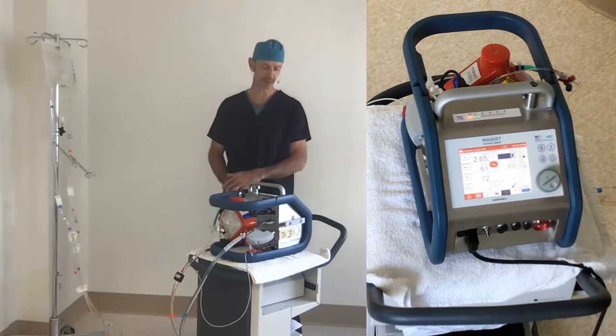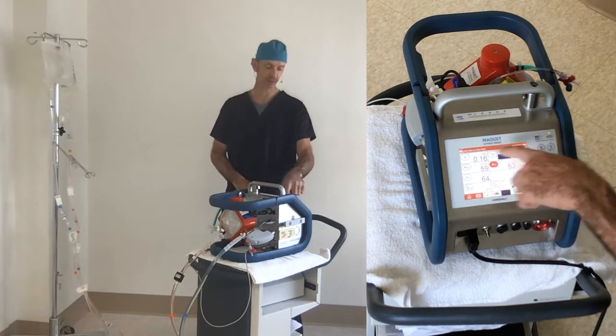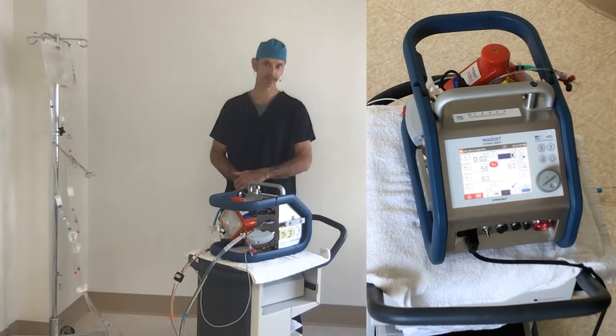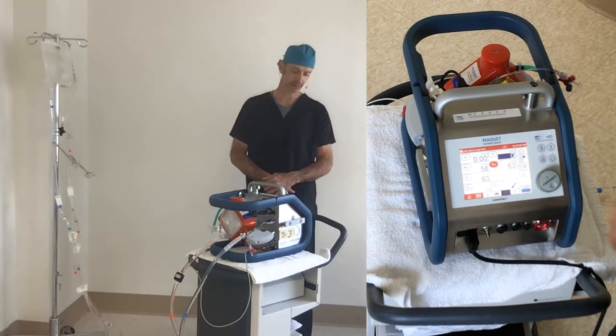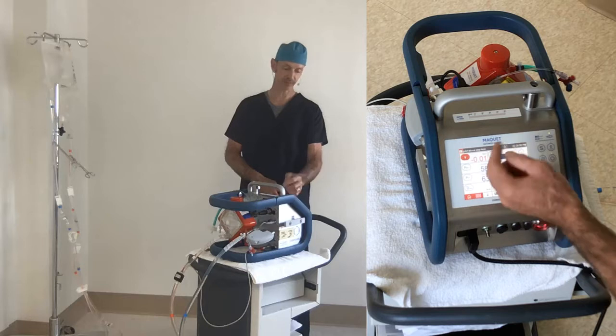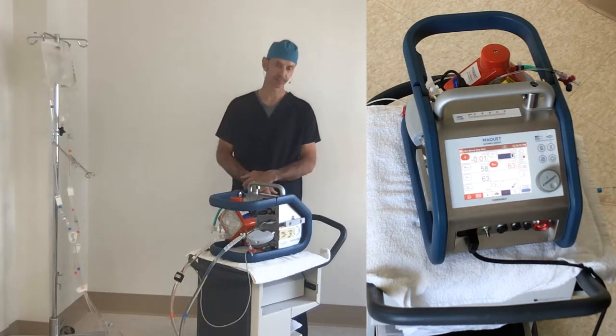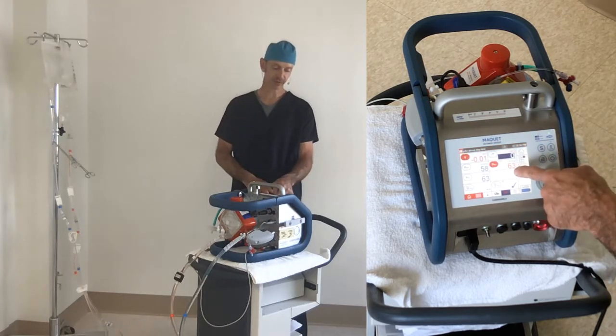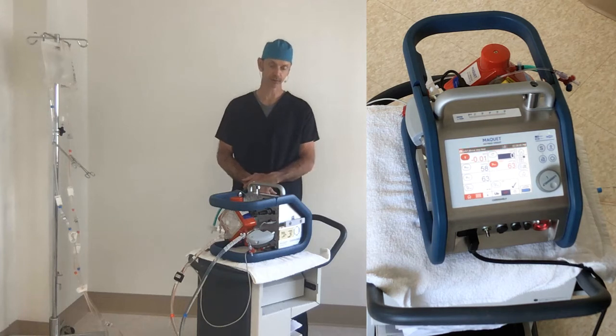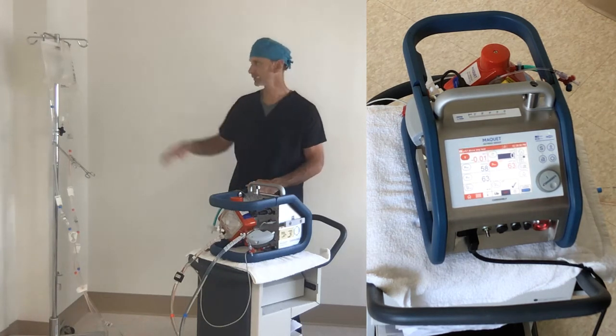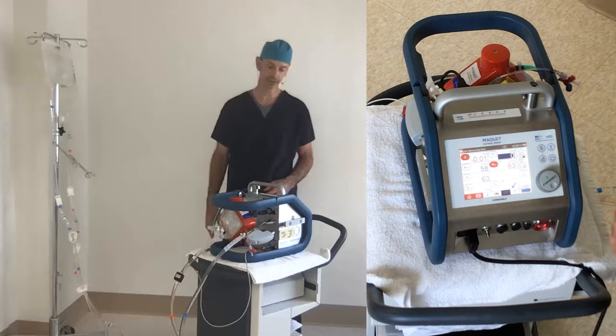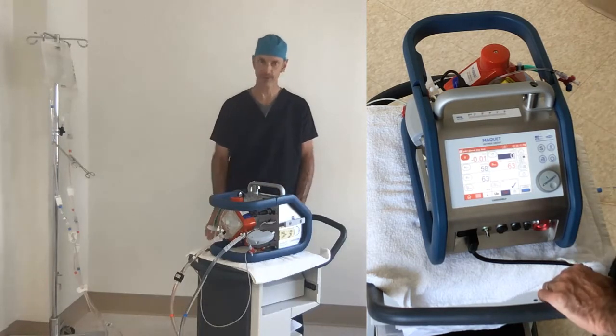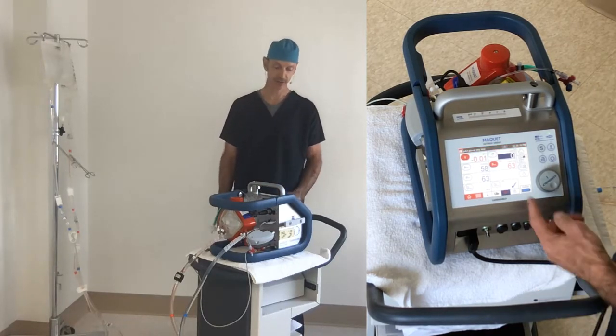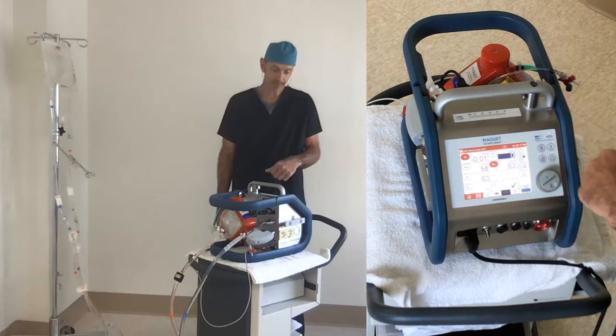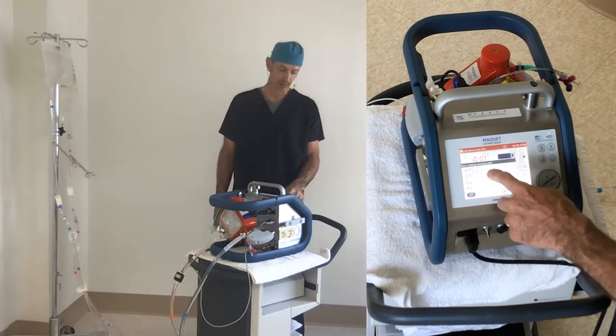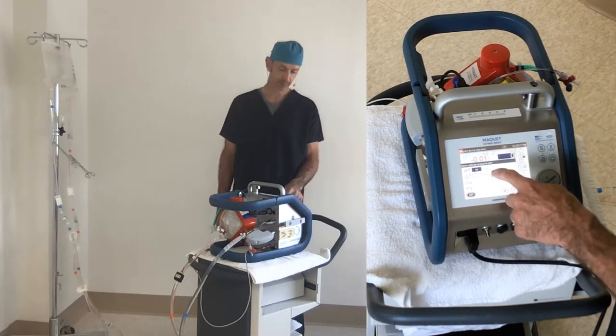to take its intervention. Now it's red because the pump has stopped, and it's telling us that the P-art is above the stop limit. Pressure is 63. I told it to turn off the pump at 44. And if we were to take this bag and lower it down so that it was less than 44 millimeters of mercury pushing down on this, then the flow would come up again. So let's raise this back up.